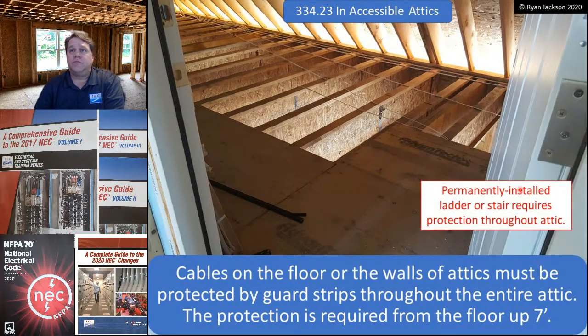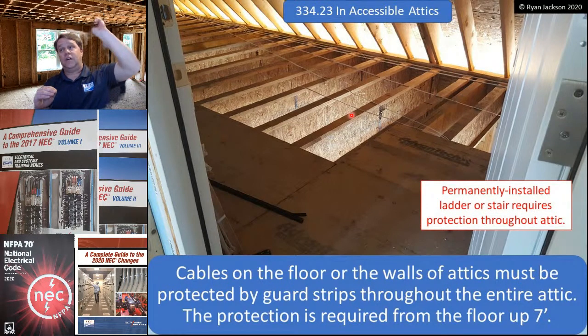Don Ganier, you sent me this picture. Here's one where you walk up the regular, carpeted stairs and go up into a bonus room, is what I've always called them. Then you open the door and you've got all this attic space. Every single wire in that attic has to be protected, because that's accessed by a permanently installed ladder or stair. I need running boards along all of those cables. The only time I would not need to do that is if they were up on the rafters 7 feet high.